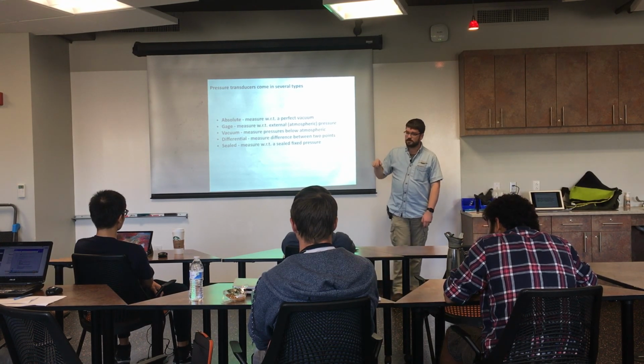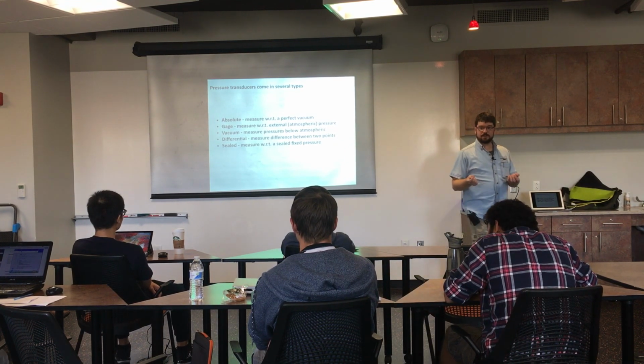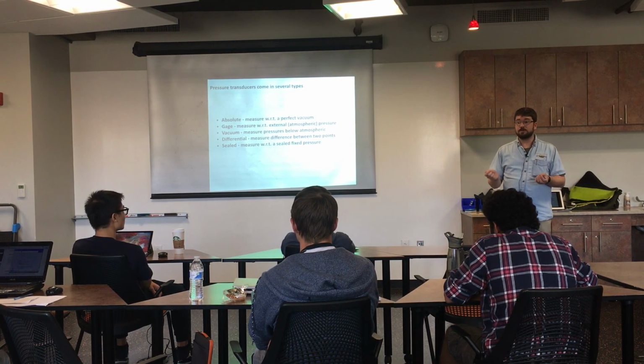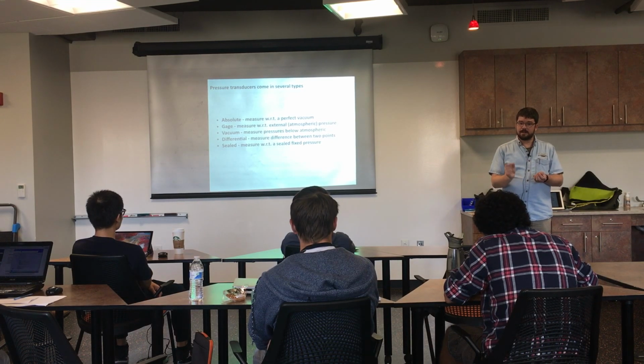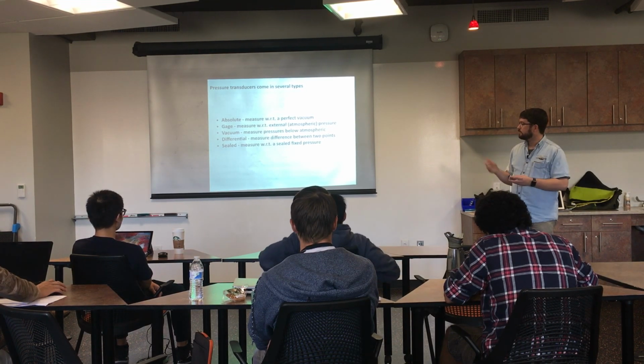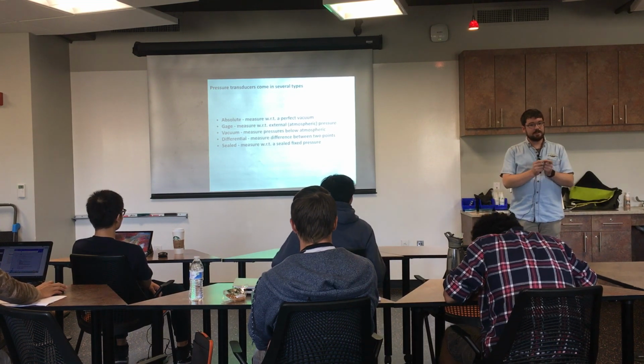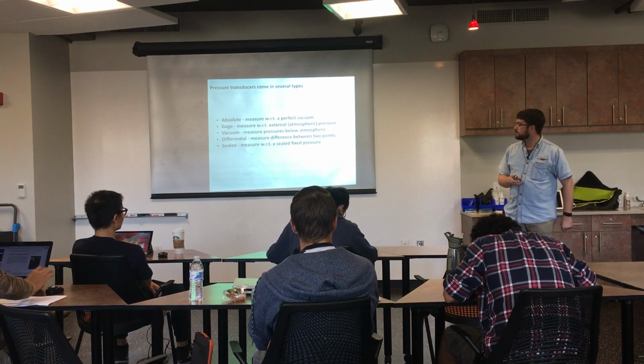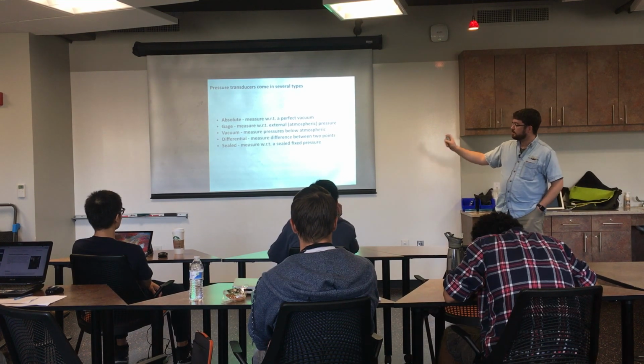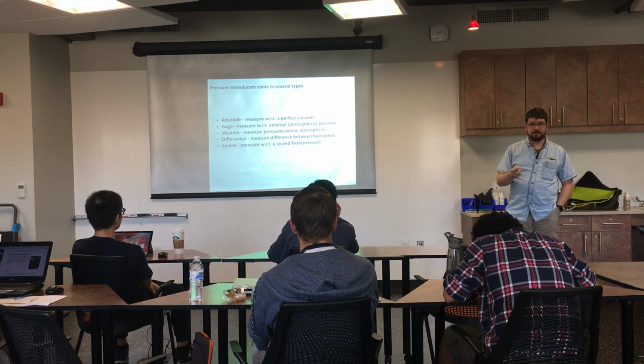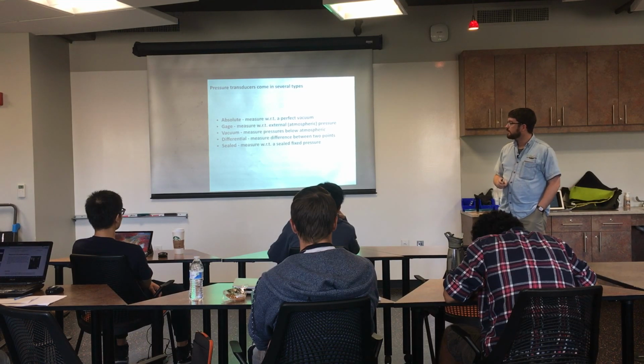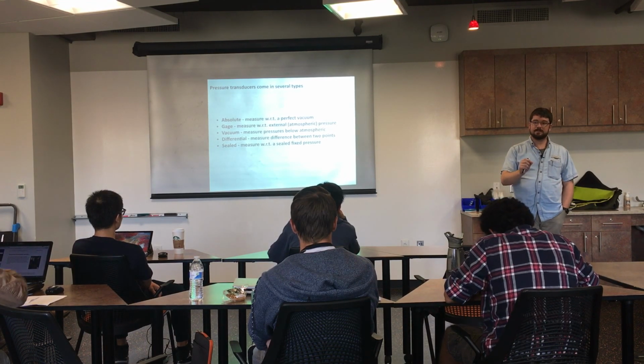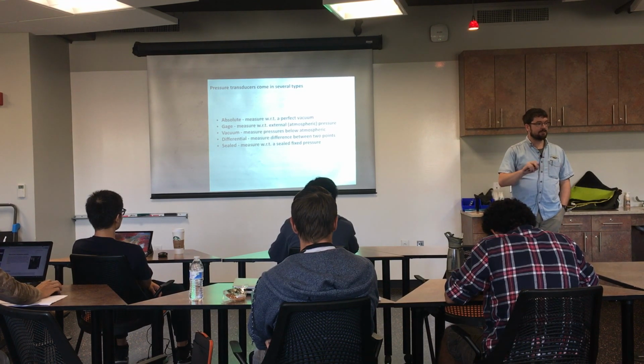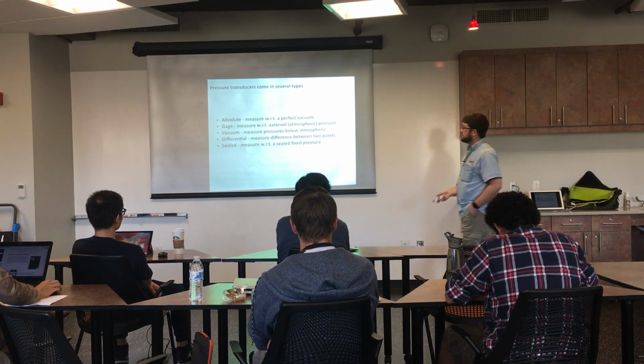And then differential transducers. A differential transducer has two inputs, and it just tells you what the pressure difference between them is. This is really handy for, say, when you have two very high pressure hydraulic lines or something, and you want to know very small differences between them. You just use a differential transducer instead of trying to measure the gauge pressure to a very high resolution. And then there are sealed transducers, which are custom. These are for very specialized applications where they seal a fixed pressure on one side of the transducer, and everything is with respect to that fixed pressure that you specified.